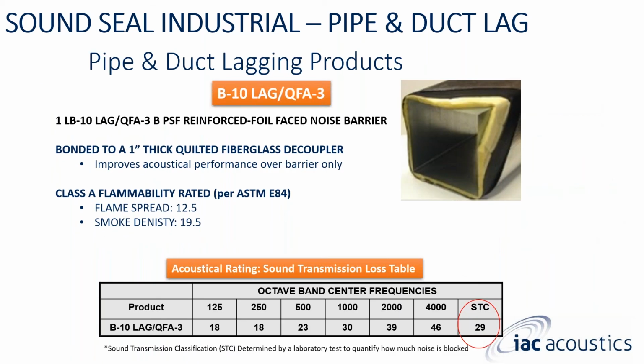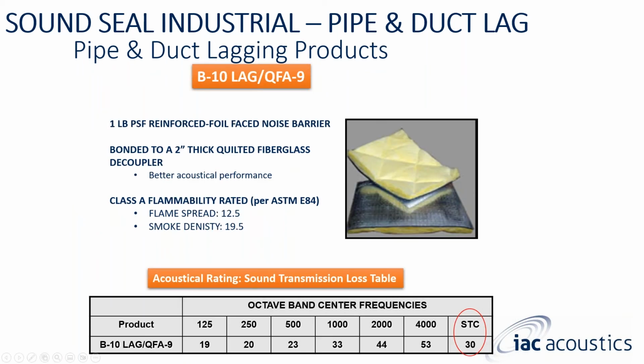The 1 inch duct lagging material, 1 inch thick, gives you an STC of 29 and roughly 6 to 7 dB added total reduction. The awesome thing about the 2 inch is that it gives you somewhere around 11 to 13. So it is better to wrap the silencer with a 2 inch thick quilted fiberglass decoupler. It is also cheaper, easier to install, and a lot lighter in weight. This is something we are working on a white paper on, and we will be issuing it to the entire engineering and consulting field in Q4.